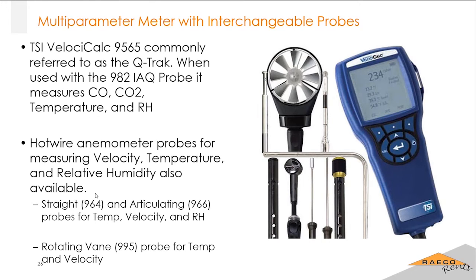Make sure you've got the applicable probe. There's a couple of options with the VelociCalc: the 964 probe and the 966 probe. They both measure the same thing, temperature, velocity, and relative humidity. But the 966 probe is an articulating probe, so you can bend and rotate it. They're both telescoping probes, so you can extend them. But if you're measuring ventilation and need to get at a certain angle, that 966 probe is what you're going to need.